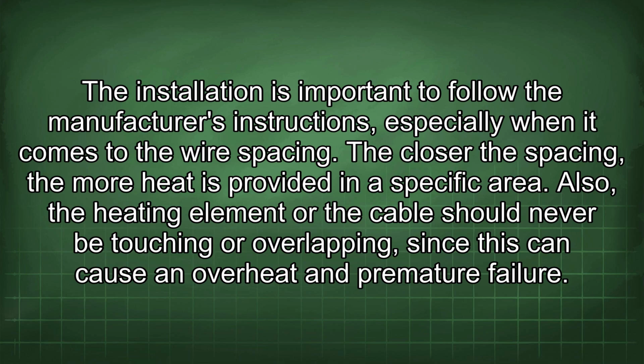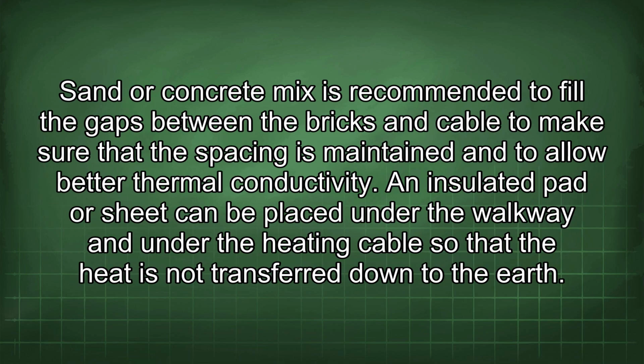The closer the spacing, the more heat is provided in a specific area. Also, the heating element or the cable should never be touching or overlapping, since this can cause an overheat and premature failure. Sand or concrete mix is recommended to fill the gaps between the bricks and cable to make sure that the spacing is maintained and to allow better thermal conductivity.